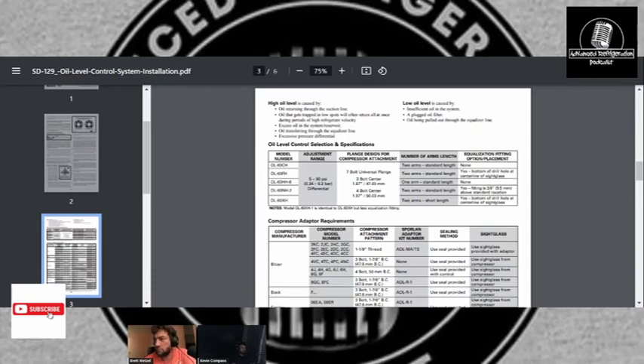On a 100% running store, it could be coming down the suction. But if you shut off the oil line and it stops, then it's probably not. And then high pressure oil systems with a valve feeding out of it, an oil differential valve, it's usually pretty easy to see that, because you'll usually have a hot line coming to it. And if you've got a float that's continuously feeding, it's usually pretty warm going into there. On an OCV, a low pressure oil system, you may not see that or feel it, because your pressure is reduced and you're sitting in a tank. You're not coming out of the separator at 150 to 180 degrees. So you may not feel that float that's just constantly feeding.